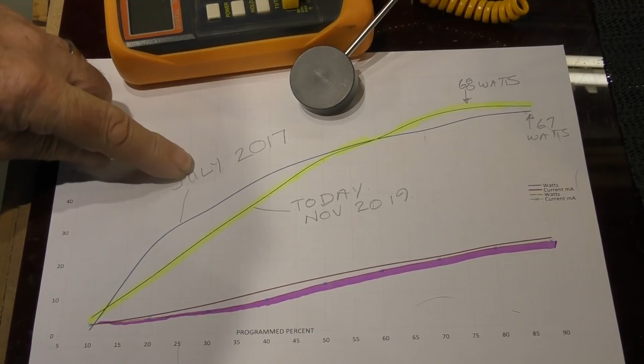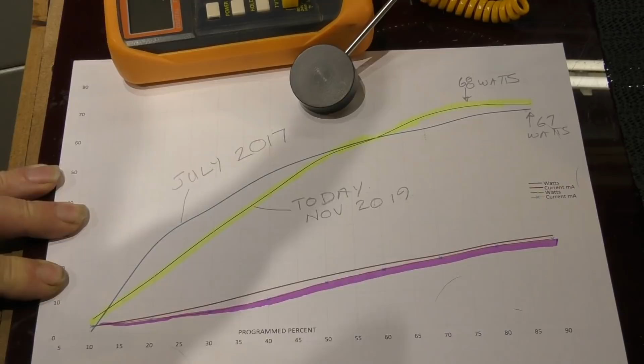Look, even though it's changed, it's actually got a very good linear relationship, which is a better relationship than the curved relationship it had 2 years ago. The current is still nice and steady, so there's nothing wrong with the power supply. The only change is with the tube itself, and if anything, the tube has got a little bit more powerful at the top here. Nothing special, so this looks like a very good tube until we look at that and see that the diagram is not telling us every part of the story.